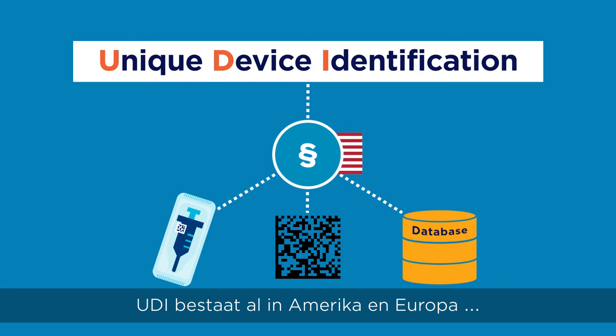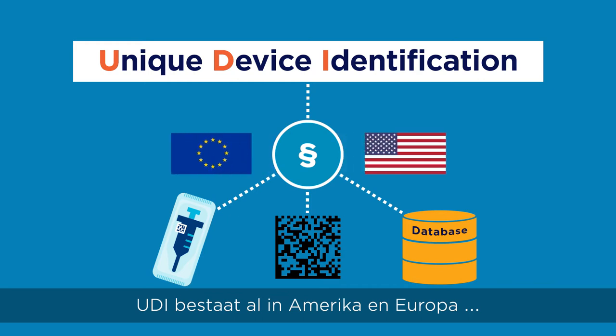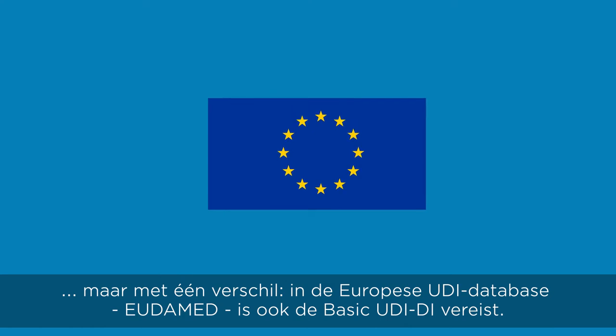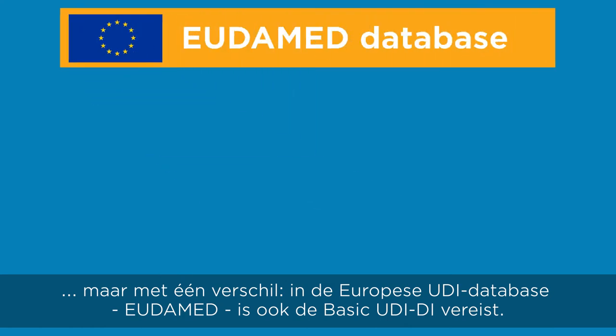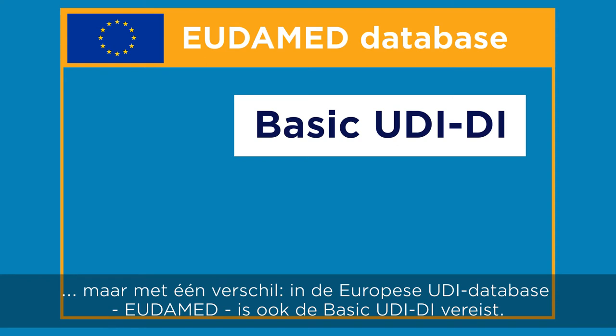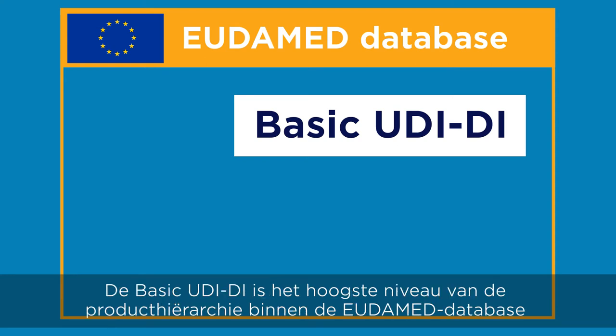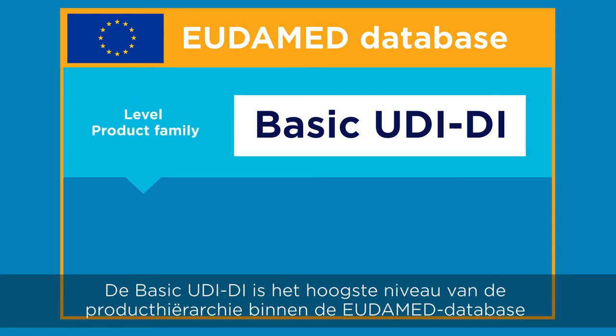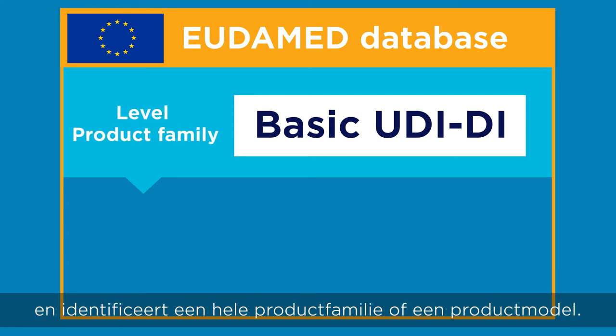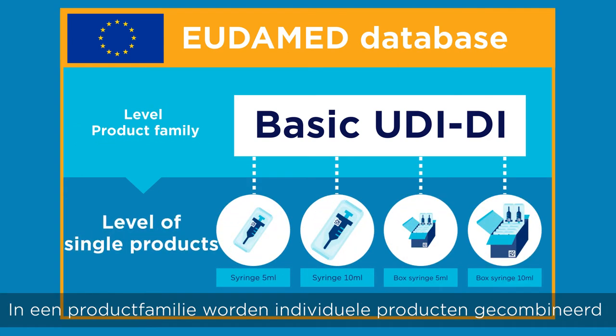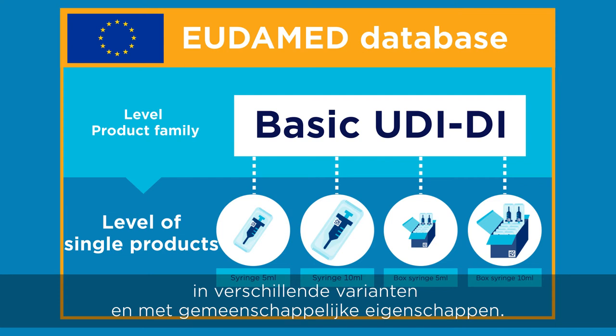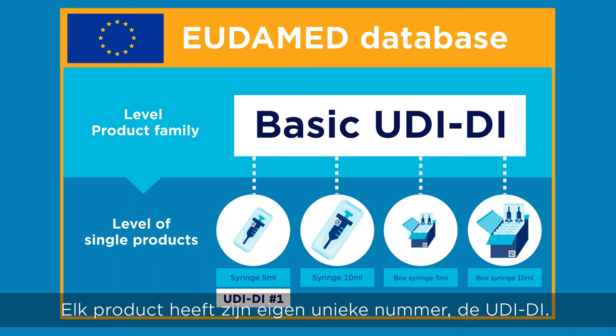UDI already exists in the United States and in the European Union, but with one difference. The European UDI regulations also require a basic UDI-DI. The basic UDI-DI is the highest level of identification of the product hierarchy within the EUDAMED database and identifies an entire product family or a product model. In a product family, individual products are combined in different variants and with common characteristics. Each product has its own unique number, the UDI-DI.